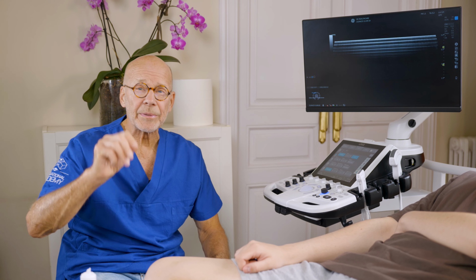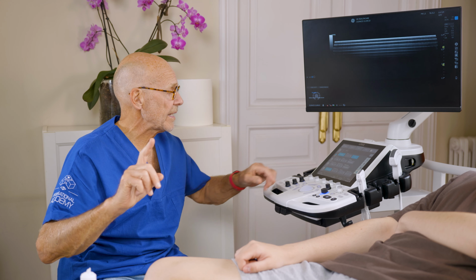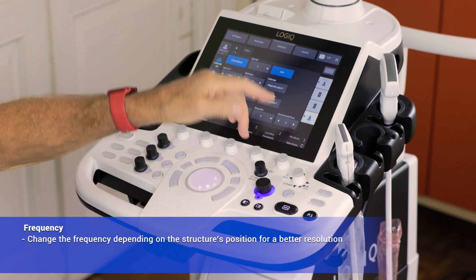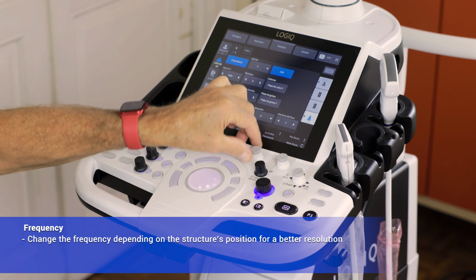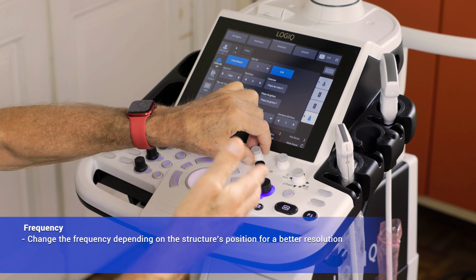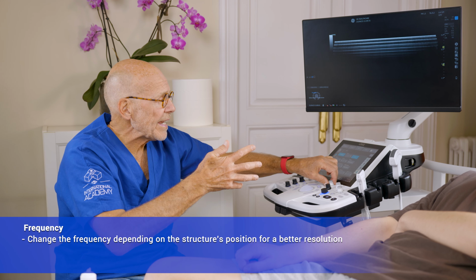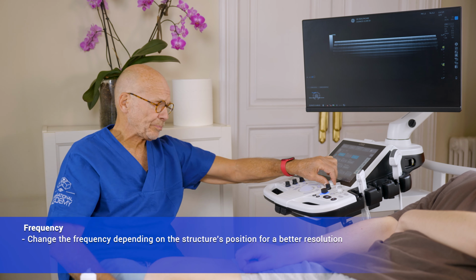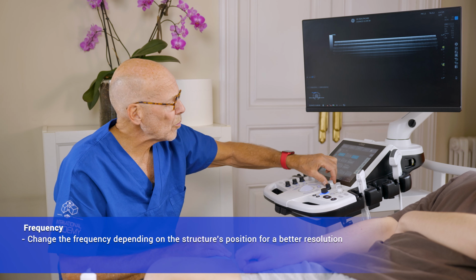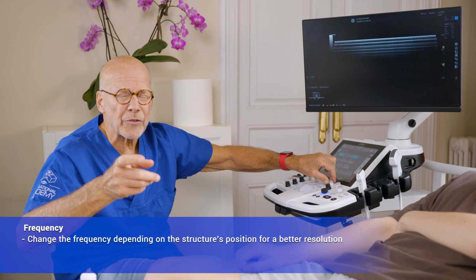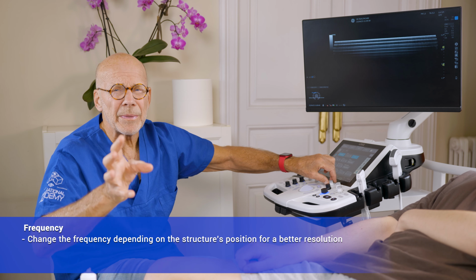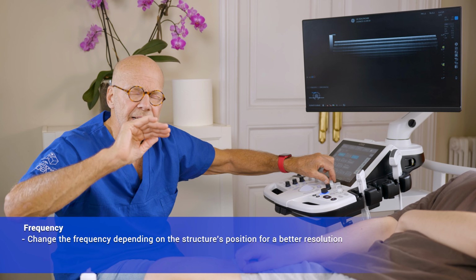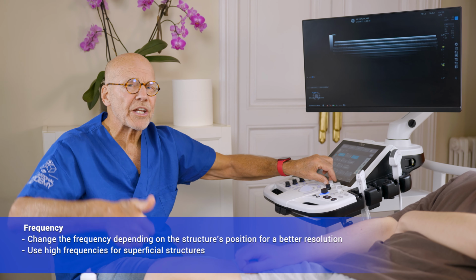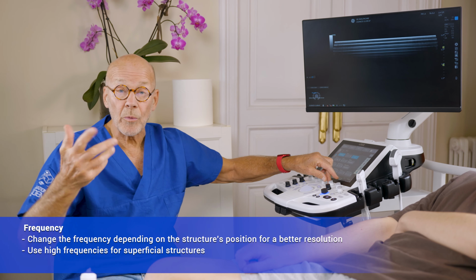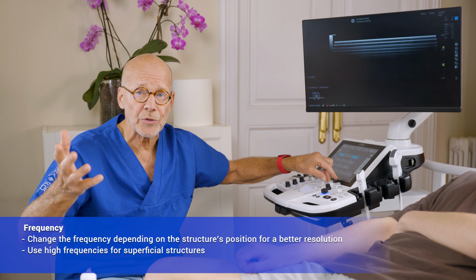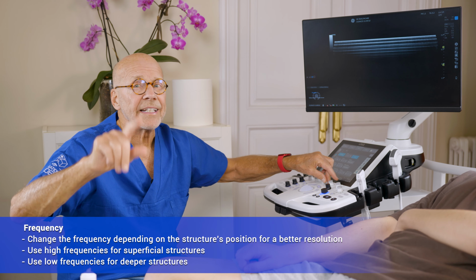Finally, or not finally, but the third adjustment that you need to consider is the frequency. On this machine, it happens to be here. It's this button. So this machine, with the probe that I'm going to use, has a range of about 4 to 12 megahertz. And so what we're going to do is change the frequency depending on where the structure that we're interested in is. If it's superficial, we can use high frequency. And that's what we want to do. Higher the frequency, the better the resolution. If it's deep, we need to lower the frequency.